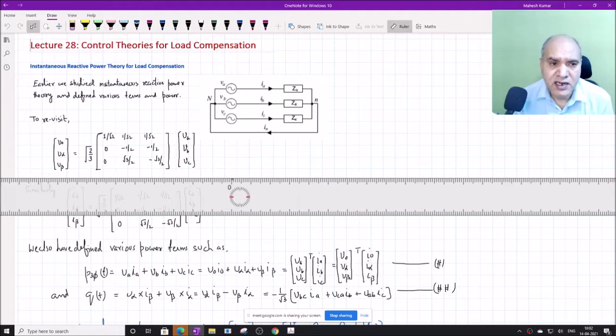Now, I have shown the diagram. If you see, this diagram is a three-phase, four-wire system, because we have the three phases and we have the fourth wire, which carries the current from the neutral wire. And this neutral wire can be grounded anywhere along the path, in a building or through a tower. And finally, this grounding becomes close to zero potential, sometimes maybe 0.2, 0.3, up to 2 or 3 volts allowed.